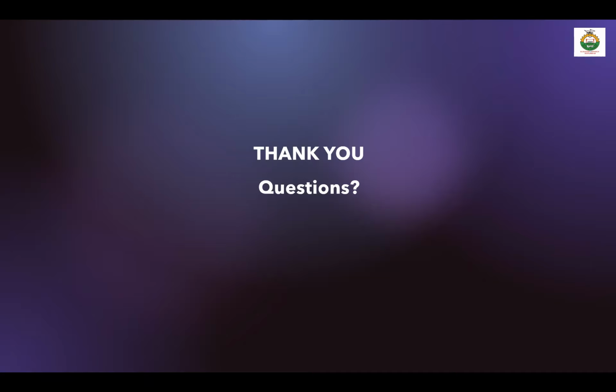Thank you so much. The reliability indices? Yes, I don't have the number on top of my head, but the UK does a regional grid system, where, for example, the Scottish part of Scotland has a separate grid from the north of England. So these grids, though they have interconnections, each have their own specific indices. But overall, I know the reason why UK reliability is high is because of the underground distribution network they apply in urban areas. We only have overhead lines in rural areas. What happens in the rural areas is that when there is any adverse weather condition, it affects them so much. We hear of power lines dropping, we hear of short circuits, and a section of the population being out of power for a period.